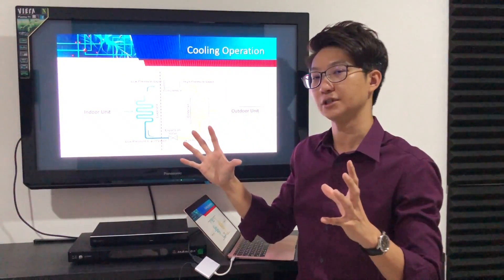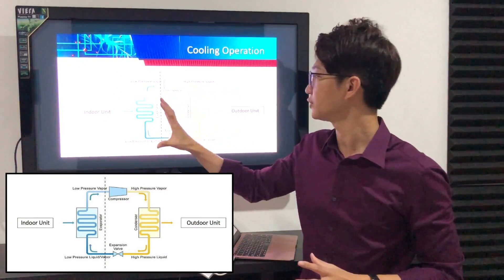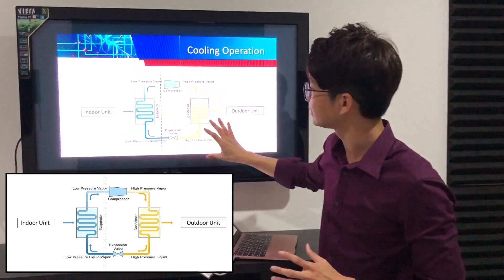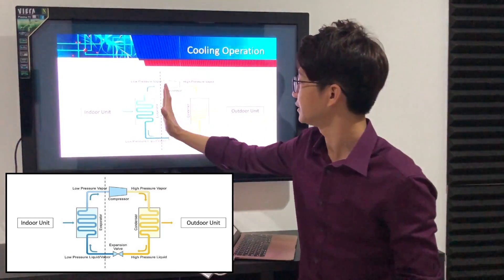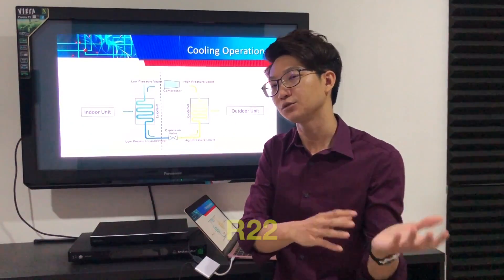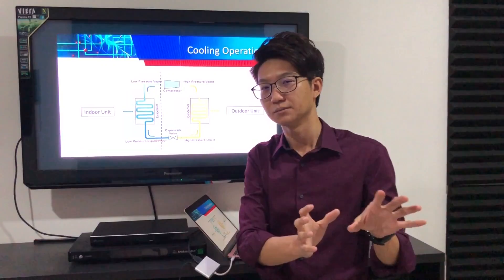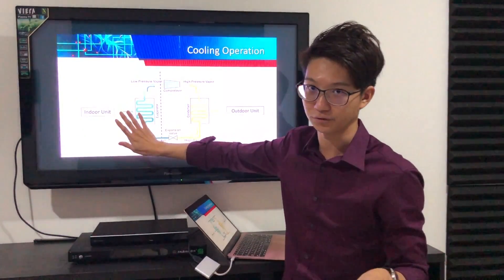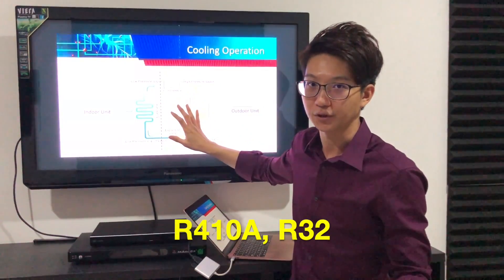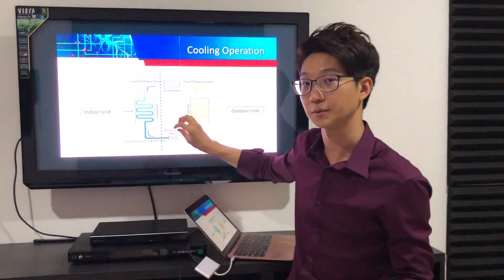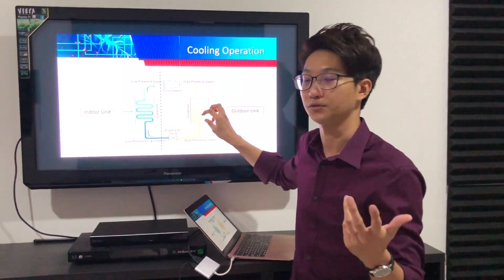During cooling mode, the indoor unit is the evaporator — this is the basic refrigeration cycle. The indoor unit is the evaporator and all the other three components are in the outdoor unit. For older R22 models, the expansion valve actually belonged to the indoor unit. But now, with newer R410A and R32 systems, the expansion valve and all three components — compressor, condenser, and expansion valve — are all inside the outdoor unit.